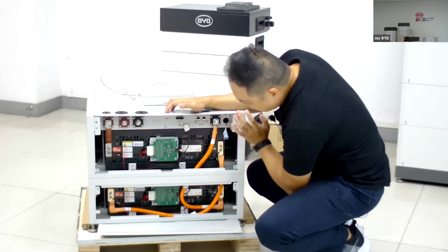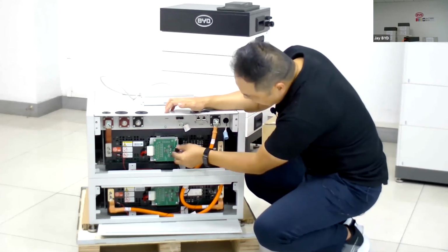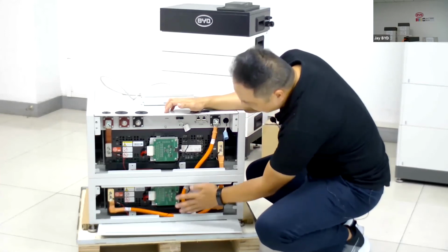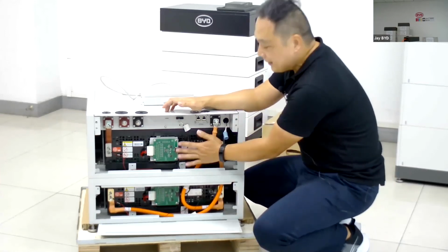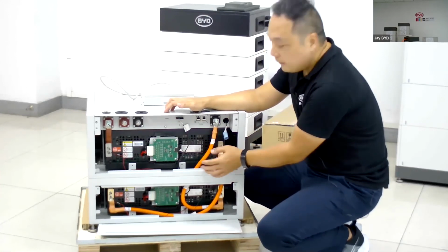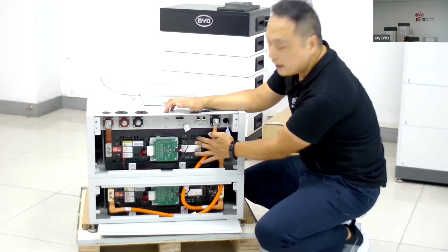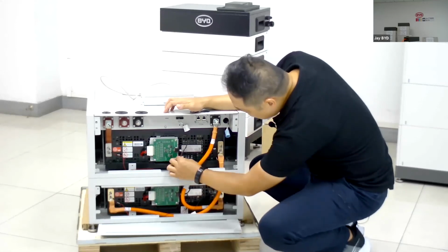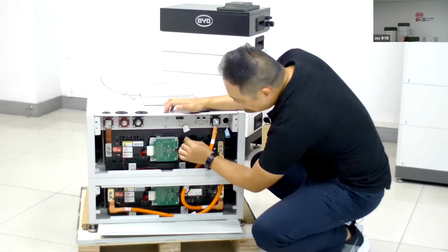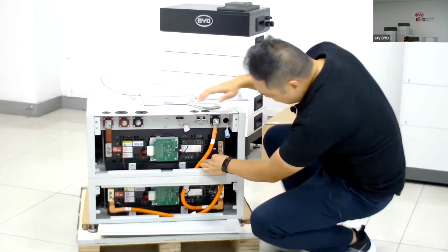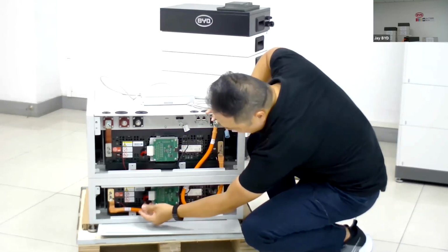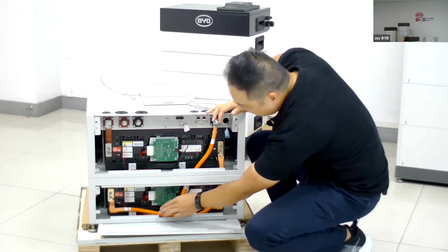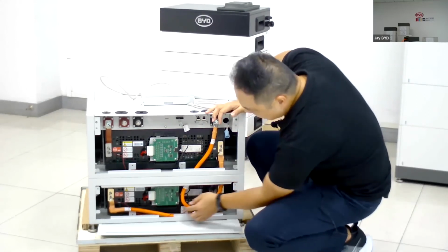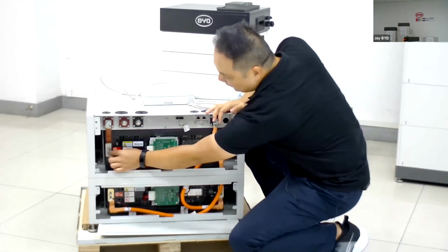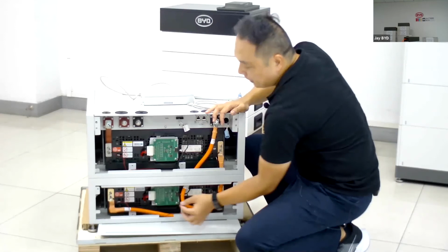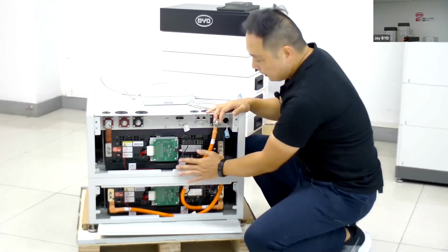Just connect - there is a plug here, and a plug to these two green cards, which we call BIC boards. It's for sampling the voltage, temperature, and signal for each battery cell. This sampling cable has positive and negative for the top battery, and also positive and negative for the bottom battery. In a few cases these cables were mixed up - mixing the top and bottom cable - and this may burn one of the cards.